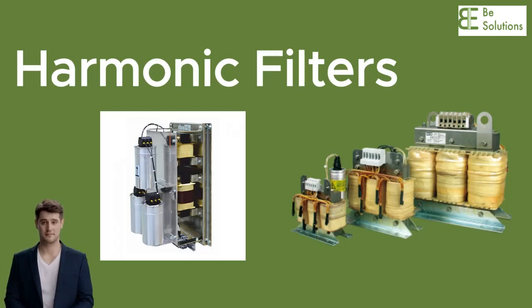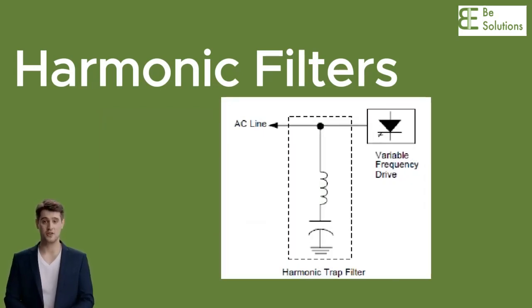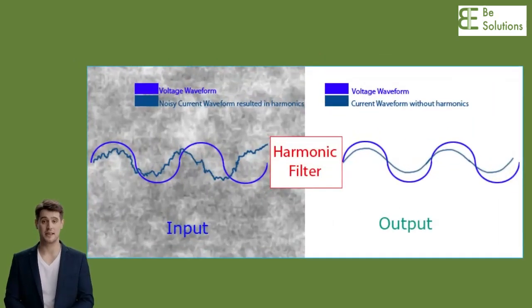Harmonic filters. Harmonic filters are more sophisticated devices designed specifically to target and eliminate specific harmonics. They usually consist of a combination of capacitors, inductors, and resistors tuned to the frequency of the harmonic to be mitigated. These filters are more complex and expensive but can provide more targeted harmonic reduction.